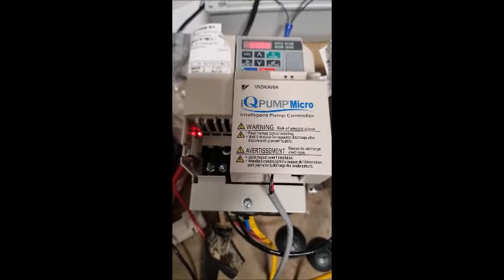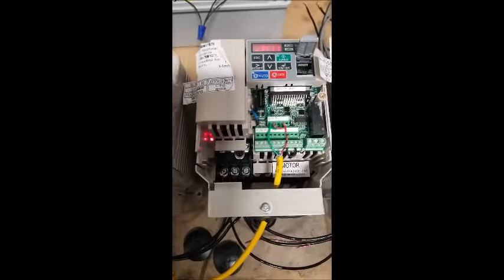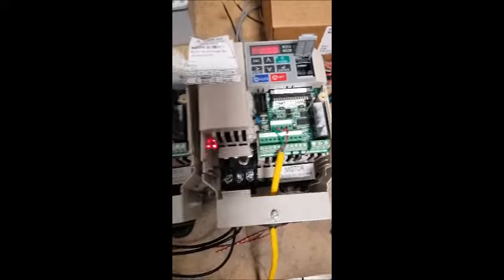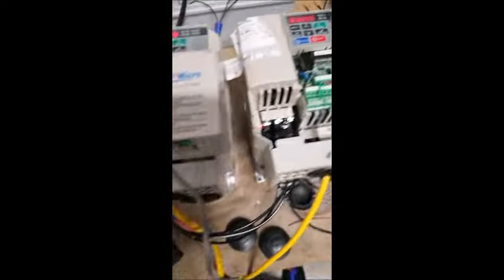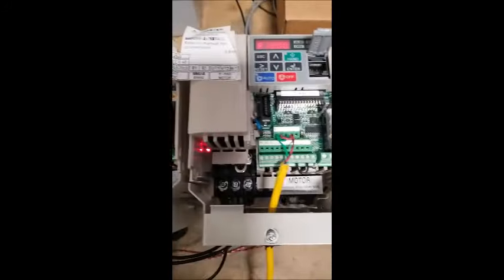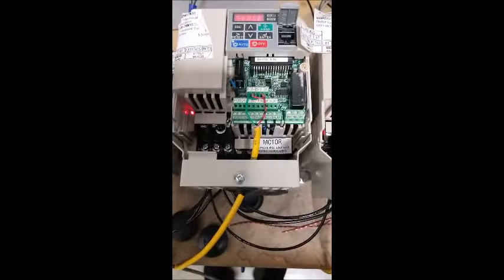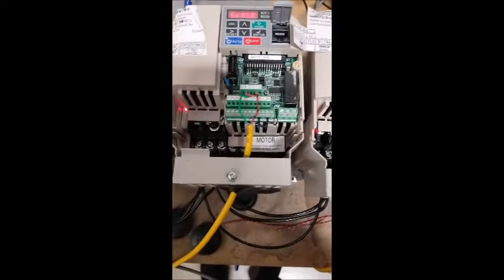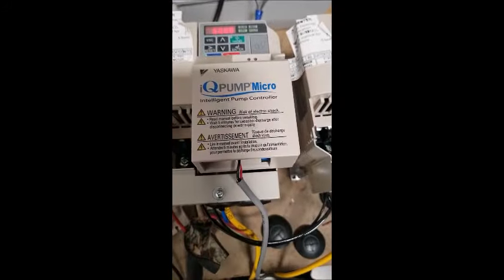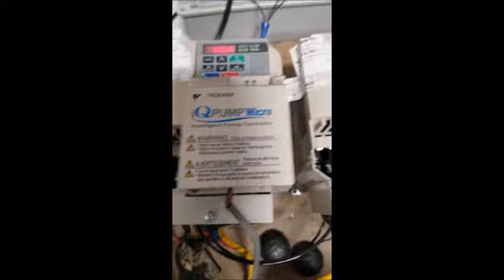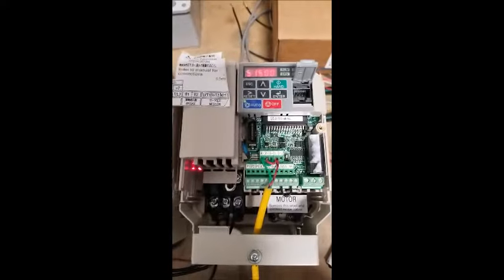Another redundancy feature of this is if you had multiple pressure transducers on the system. As you can see, I only have one hooked up, but if you had multiples, each drive can look at its own pressure transducer, and each drive can look to the communications for a pressure. So if your pressure transducer fails on one drive, it looks over to the network for a pressure reading, which is what it's doing now for the 2 drives that don't have transducers.